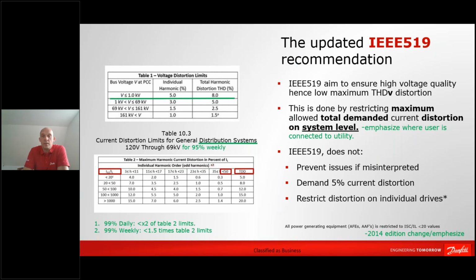As we are often met in the market with requirements of meeting specific standards, I would like here to explain a bit about the standards that you normally meet in the Middle East and Africa, which is the IEEE 519 recommendation. The IEEE 519 recommendation is not a product recommendation, it's a system recommendation. And that means that it doesn't apply for individual products. It applies only for your installation.